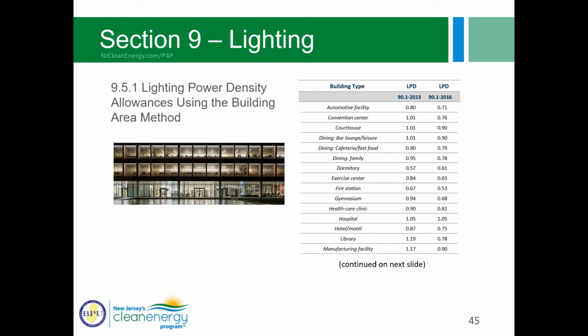Looking at the whole lighting for the building, this is usually one of the bigger ticket items. So it comes in two flavors: the building area method and the space by space method. And a real quick refresher on these for those that may not be completely familiar with it. So the building area method is the allowed lighting derived from a representative mix of spaces to get a total number. This allows flexibility between the spaces so long as the total is less than the allowance.